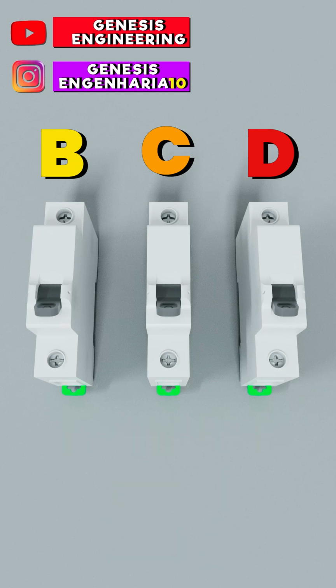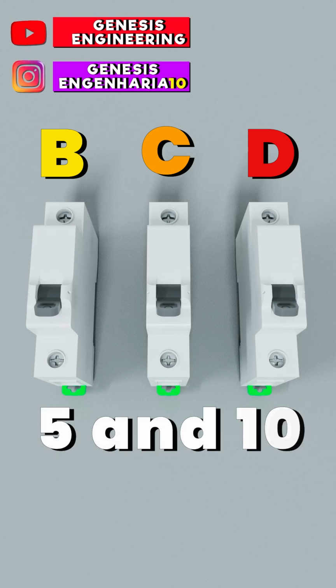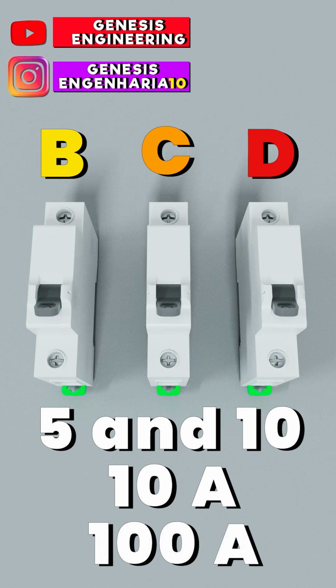The MCB with curve C, the supported current for short circuit protection, is between 5 and 10 times the rated current, so with a 10 amps MCB, it will withstand a short circuit current of maximum 100 amps.